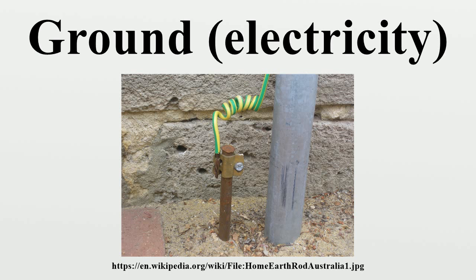In the past, water supply pipes were often used as grounding electrodes, but this was banned where plastic pipes are popular. This type of ground applies to radio antennas and to lightning protection systems. Permanently installed electrical equipment usually also has permanently connected grounding conductors. Portable electrical devices with metal cases may have them connected to earth ground by a pin in the interconnecting plug. The size of power ground conductors is usually regulated by local or national wiring regulations.